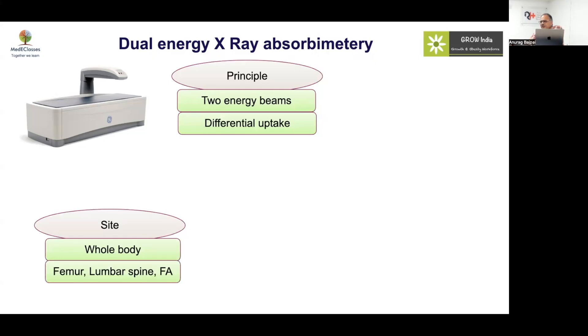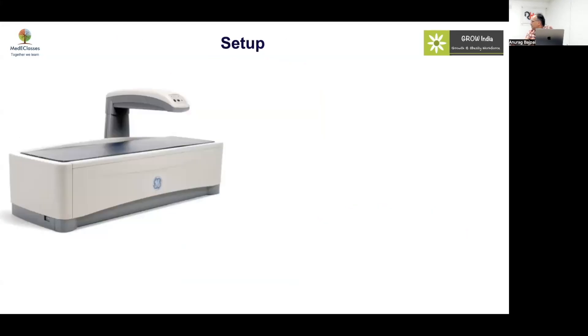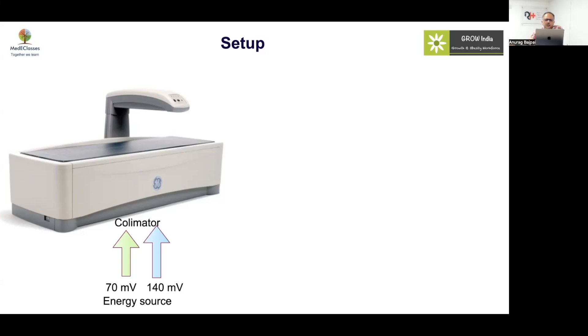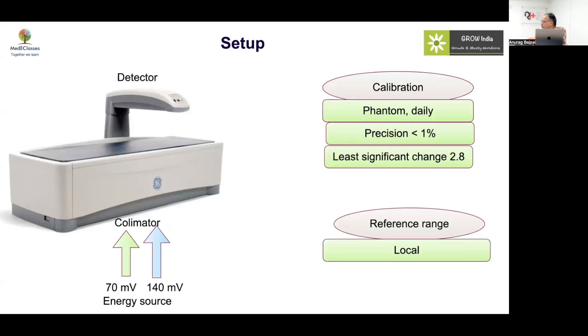You can scan the whole body, femur, lumbar spine, or forearm. There are many confounding factors, and the reference database used is also important. The energy source produces two beams at 70 and 140 kilovolts, which are collimated and directed to a detector while the person lies in between. Calibration is done using a phantom of known density; precision should be less than 1% variation.